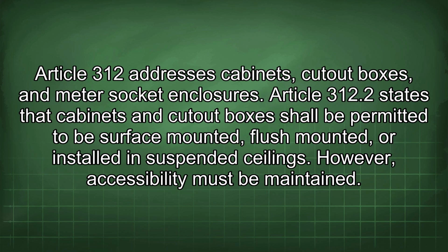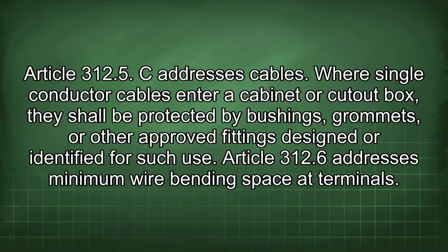Article 312 addresses cabinets, cutout boxes, and meter socket enclosures. Article 312.2 states that cabinets and cutout boxes shall be permitted to be surface-mounted, flush-mounted, or installed in suspended ceilings. However, accessibility must be maintained. Article 312.5 C addresses cables. Where single conductor cables enter a cabinet or cutout box, they shall be protected by bushings, grommets, or other approved fittings designed or identified for such use.